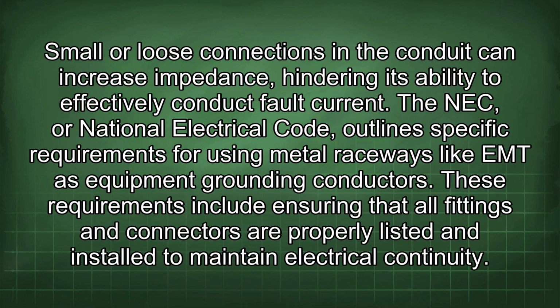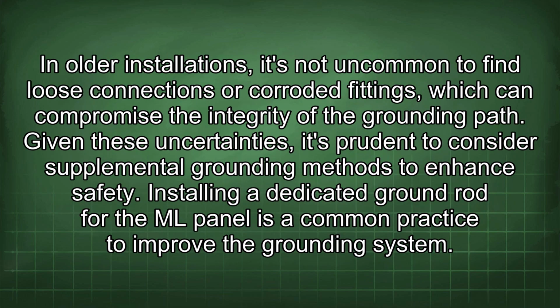Small or loose connections in the conduit can increase impedance, hindering its ability to effectively conduct fault current. The NEC, or National Electrical Code, outlines specific requirements for using metal raceways like EMT as equipment grounding conductors. These requirements include ensuring that all fittings and connectors are properly listed and installed to maintain electrical continuity. In older installations, it's not uncommon to find loose connections or corroded fittings which can compromise the integrity of the grounding path. Given these uncertainties, it's prudent to consider supplemental grounding methods to enhance safety.